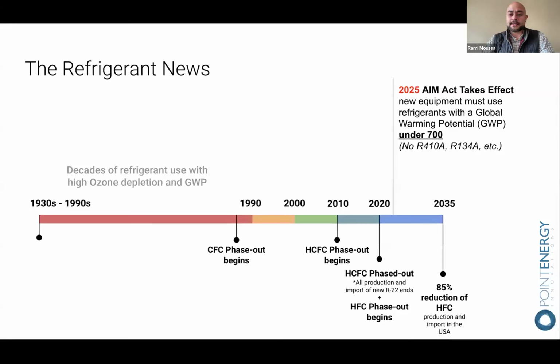So in the last couple of years, we've seen the phase-out of R22, and now even more conventional, more frequently used R410A. So equipment that was basically installed last year will not really be able to be maintained - will not be able to be replenished with leaked refrigerant - in 2035.